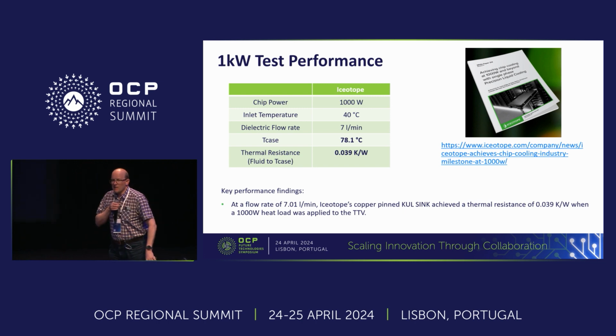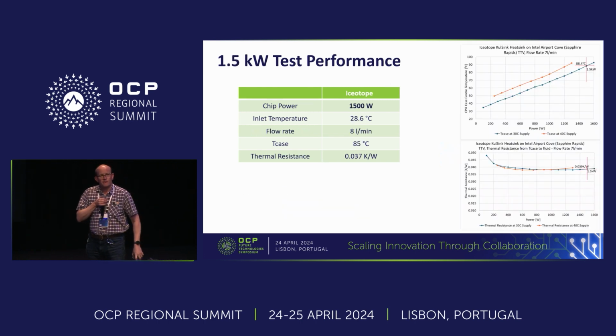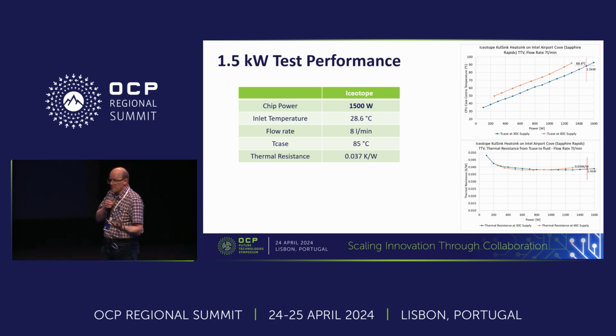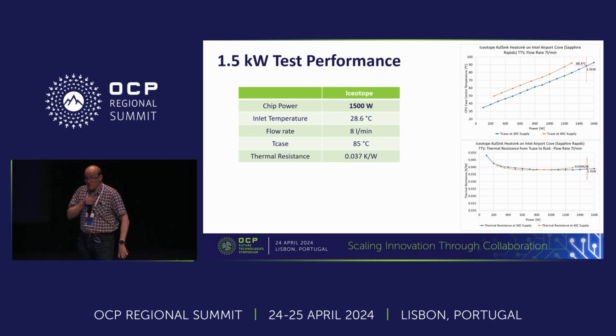What we're going to say for the first time today, what we've not said prior to now, is we've done some testing at 1.5 kilowatts. Same test setup as before. True, to keep the overall case temperature manageable, we dropped the inlet temperature a little bit and increased the flow a little bit, but it's effectively the same thermal resistance we were looking at before.